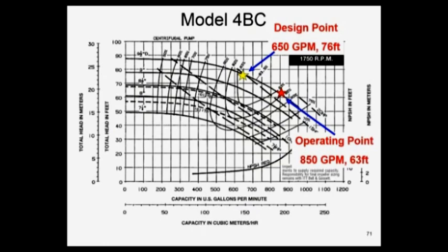If my pressure drop is 63 feet versus 76, what is my flow rate? I'm not underperforming flow-wise, I'm overperforming. So you see the red star, the yellow star is design, it's where you thought you'd be. The red star is where you really are, and if you take the red star on that impeller of 9.5 inches, that's where you've got to be with 63 feet to the vertical axis, read straight down, what is your flow rate, 850 GPM. So you're flowing 850, only requirement was 650, and that's why it's noisy. You've got high velocity going on, you've got a noisy system because you're overflowing.